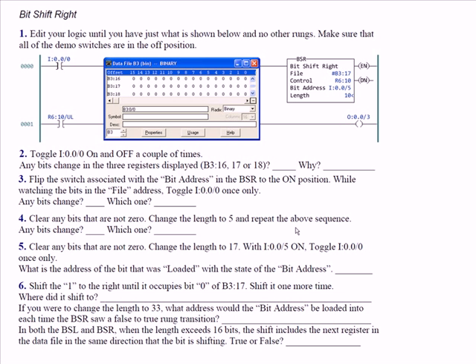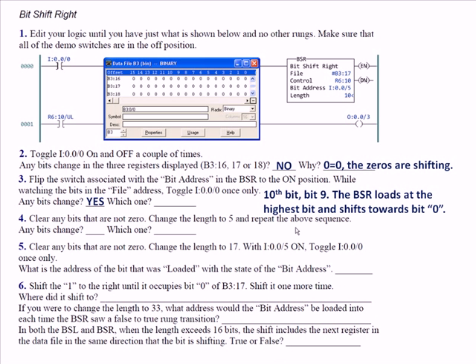In the lab, once your logic is edited, downloaded, and online with B3:16, 17, and 18 displayed, toggle Input 0 on and off a couple times. With all switches off, the rung goes false-true-false-true but there's nothing to load but zeros — it is actually shifting, but shifting 0 to 0 is still 0, so no bits appear to change in registers 16, 17, or 18. Now flip the switch for the bit address — Input 5 — to on, then toggle Input 0 once only. Did any bits change? Yes — the tenth bit, or bit 9. The BSR loads at the highest bit and shifts toward bit 0, just the opposite of the Bit Shift Left.